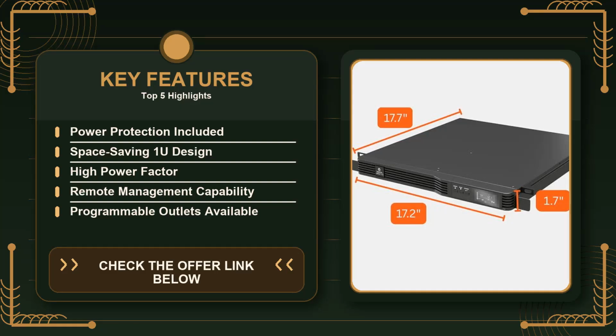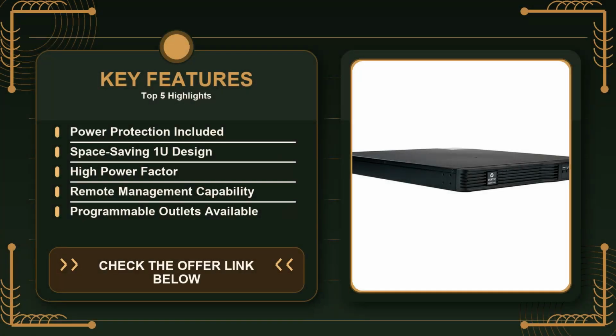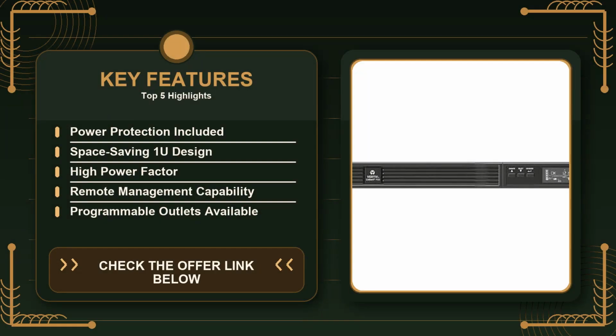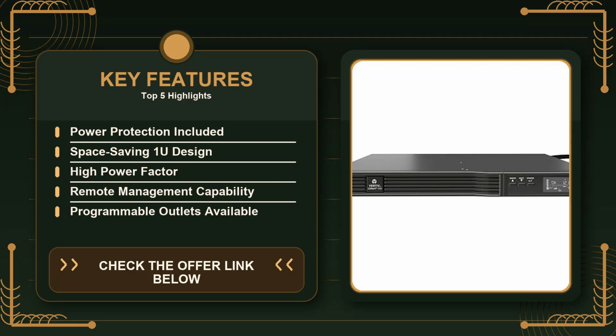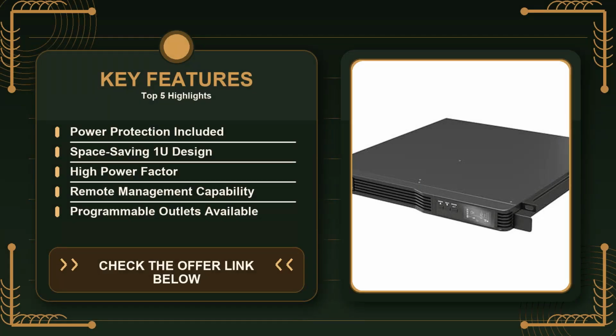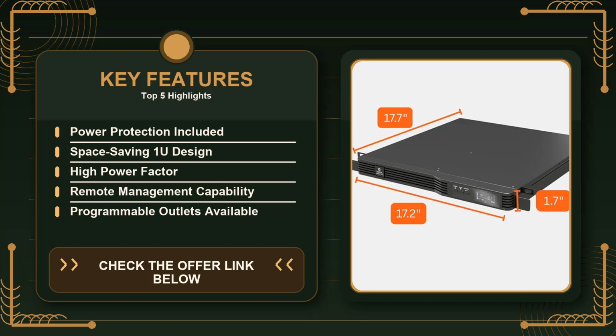At full load, you're looking at roughly 8 to 10 minutes before the battery is exhausted, enough time to initiate a proper shutdown, but not enough if you need to keep critical services running through a prolonged outage. If your environment experiences frequent, extended brownouts, you'll want a UPS with a larger battery pack or the ability to hot swap batteries without taking the unit offline. The PSI5 doesn't support hot swap battery modules, so you'd have to shut down the UPS to replace them, which can be a hiccup in a high availability scenario.